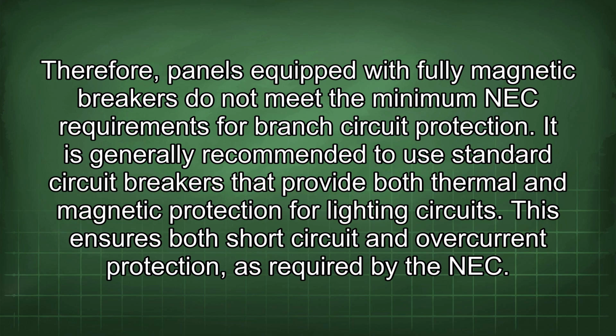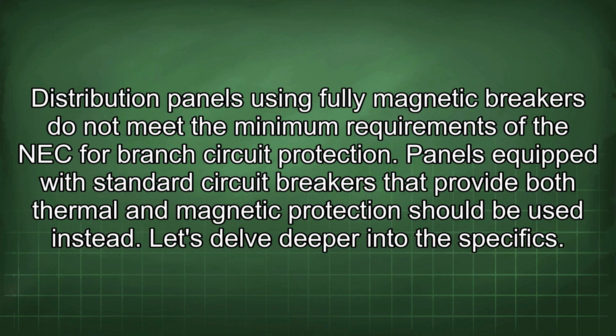It is generally recommended to use standard circuit breakers that provide both thermal and magnetic protection for lighting circuits. This ensures both short-circuit and overcurrent protection as required by the NEC. Distribution panels using fully magnetic breakers do not meet the minimum requirements of the NEC for branch circuit protection. Panels equipped with standard circuit breakers that provide both thermal and magnetic protection should be used instead.